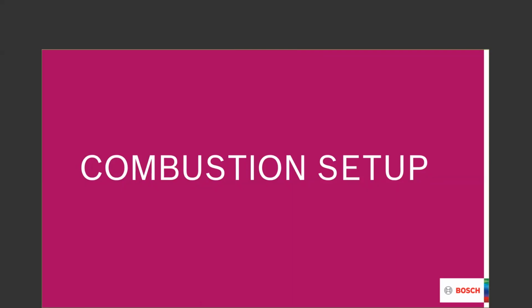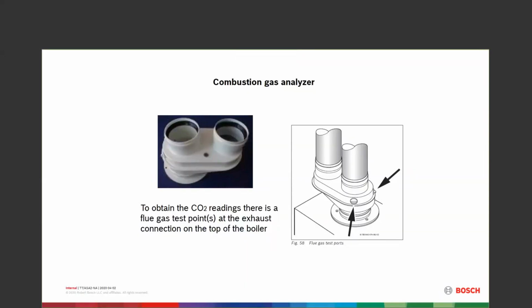When we get into the combustion setup of this, there are 2 taps for flue gas ports on the vent, one on each side. They both go to the same place. Just use one. You don't have to use them both. One of them you might even not be able to get to. It might be too close to the wall. That's why they put 2 of them in there.